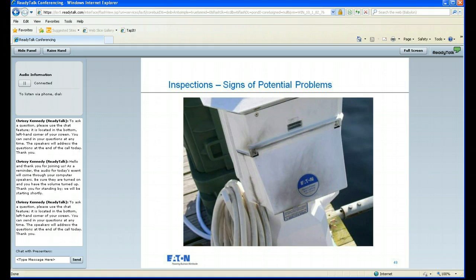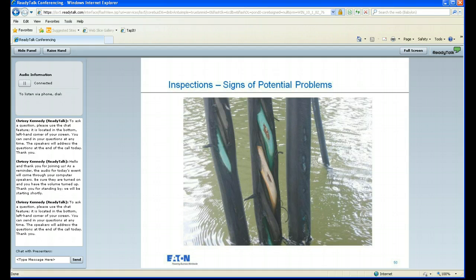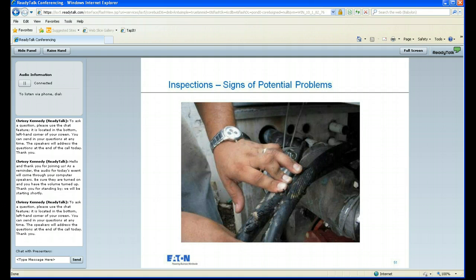Any sign of burning, arcing, melting, fire, smoke, anything like that, is also a sign of a potential problem. Any exposed cables, whether from movement of the docks, scraping, boats running into them, anything where you have exposed conductors. In this picture, you can see there's some exposed copper on these cables, probably due to dock movement or some other source. But anything like this, especially if you see it on a green wire, that's your ground wire, is a sign of a really big problem.